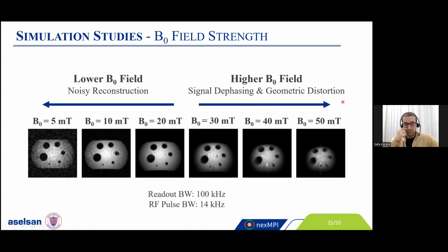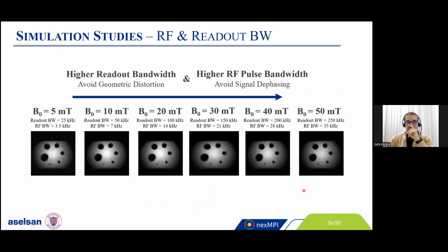In the literature, there are different low field MRI scanners which utilize a B0 field of 50 millitesla, and our aim is also to go for that. So we try to adjust our pulse sequence parameters in order to have the same image quality even in the case of a higher B0 field. To do that, we adjust the readout bandwidth and the RF pulse bandwidth of our pulse sequences.